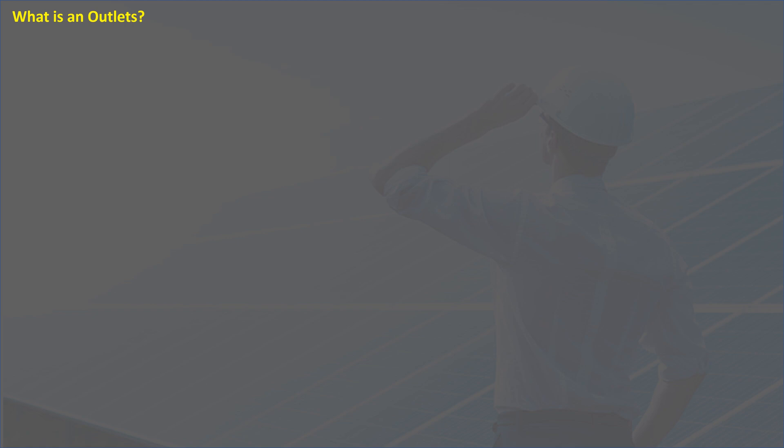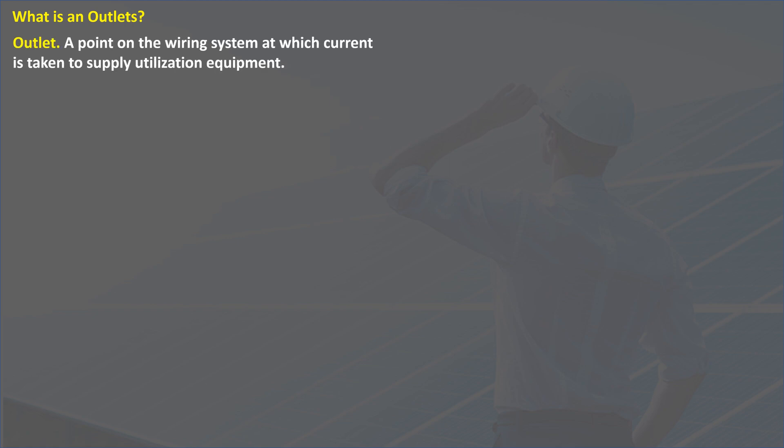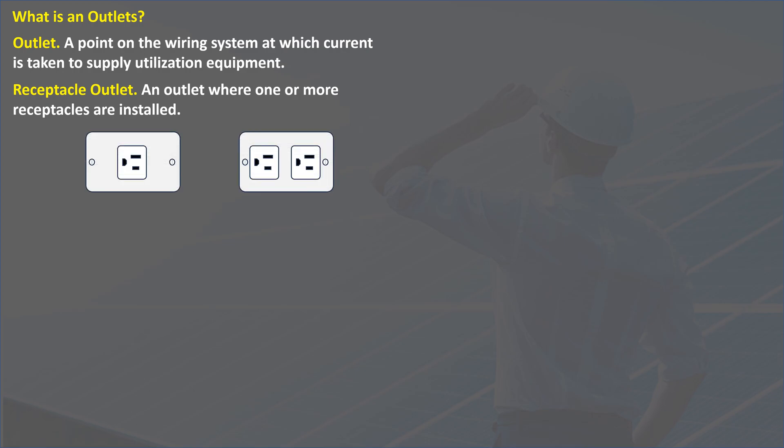First, what is an outlet? As defined in the electrical code, an outlet is a point on the wiring system at which current is taken to supply utilization equipment. The definition of a receptacle outlet is an outlet where one or more receptacles are installed. Photos show typical receptacle outlets. A receptacle is always an outlet, but an outlet is not only a receptacle.